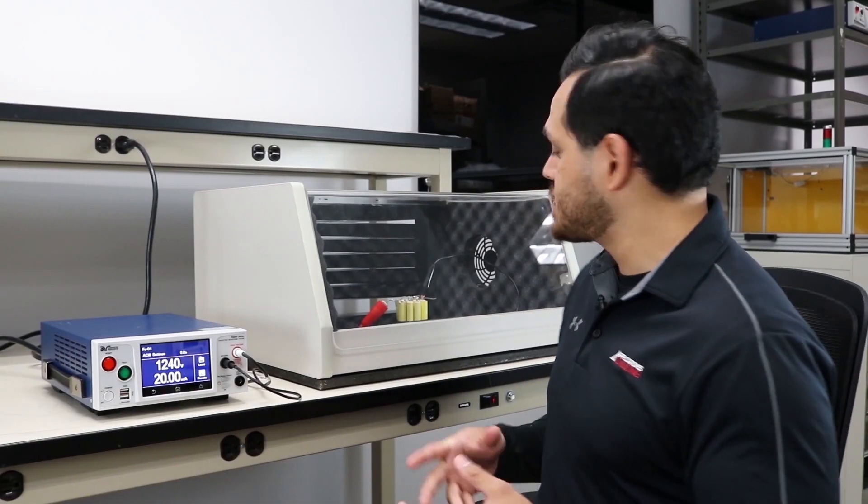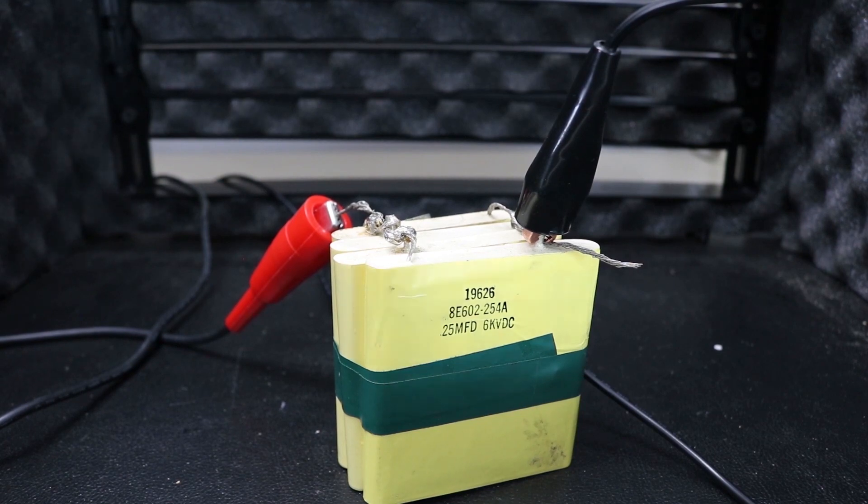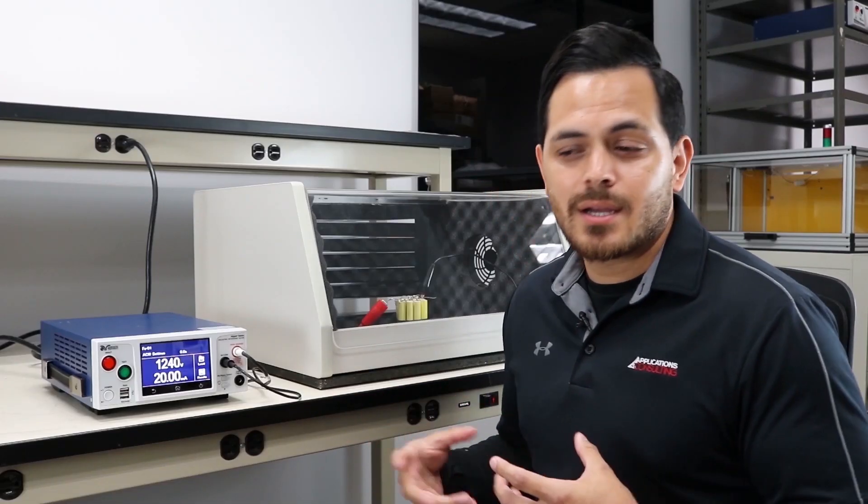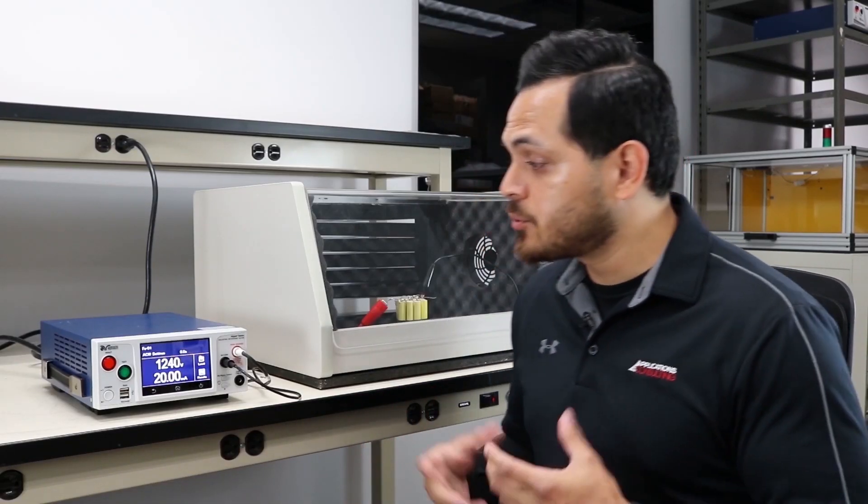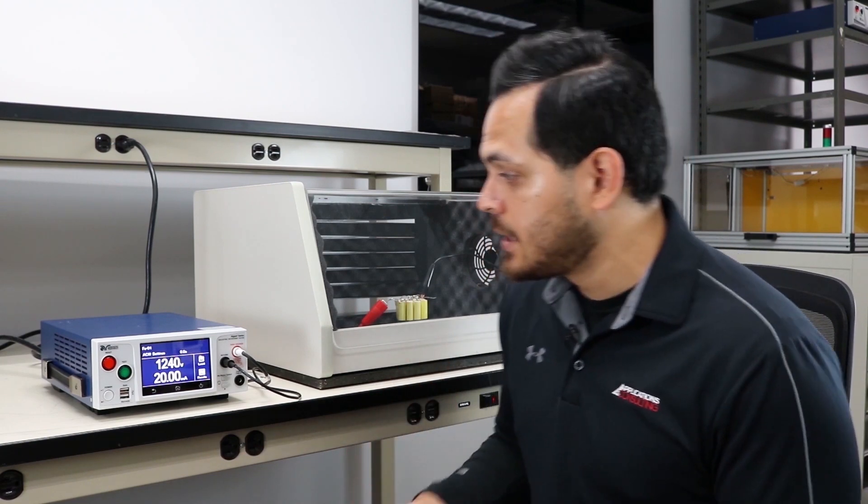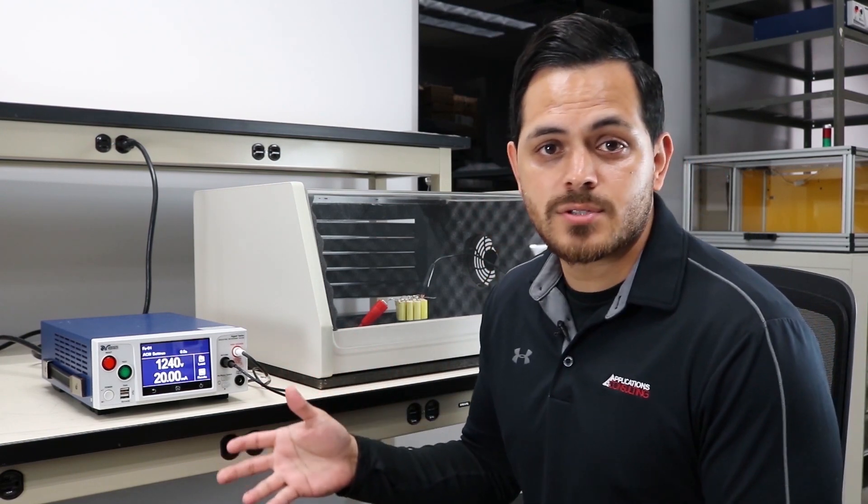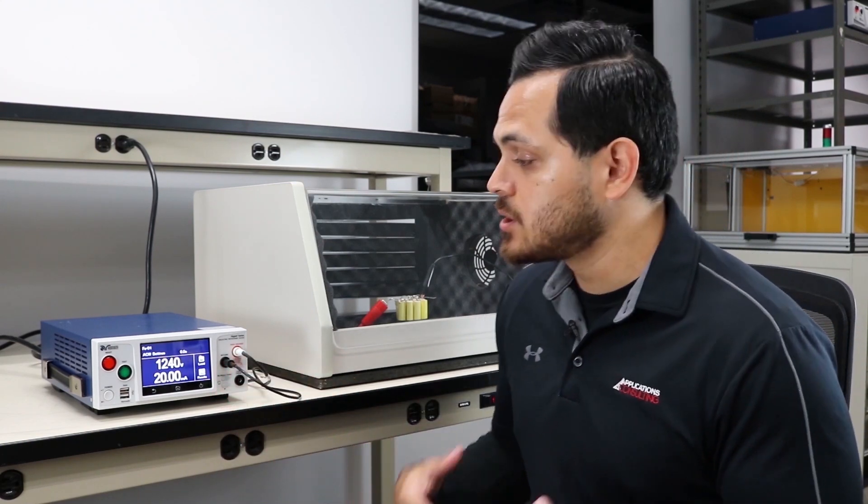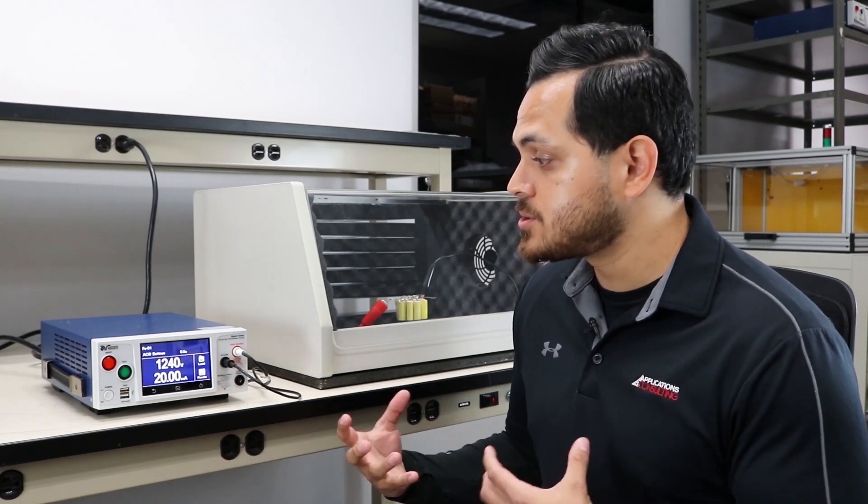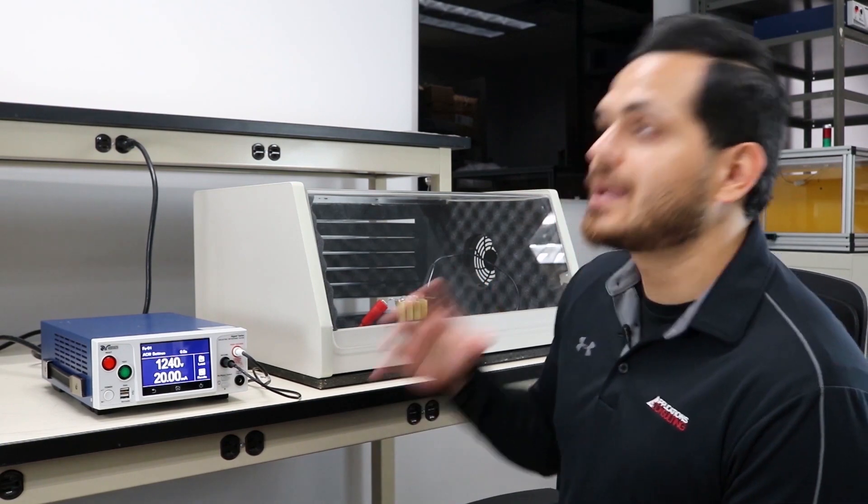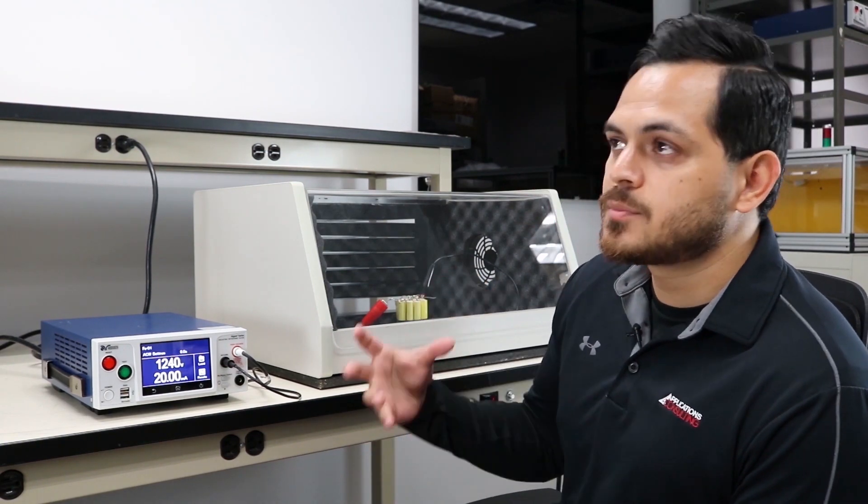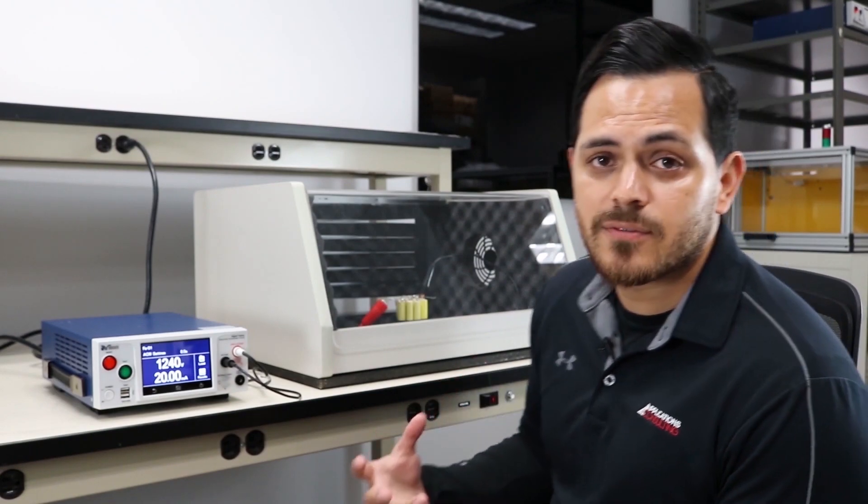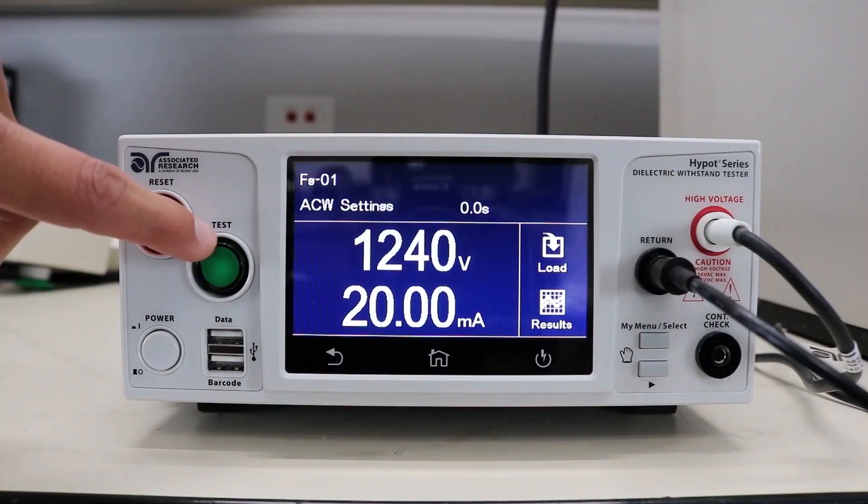All right, so as I said earlier, here we have some capacitors in parallel simulating a highly capacitive product. We're going to run a normal AC hypot test at 1240 volts - that's very standard. Our high limit is at 20 milliamps, that's the most our tester can output. Again, this is simulating a customer's highly capacitive motor or a thousand feet of cable spooled together. We'll run this test.